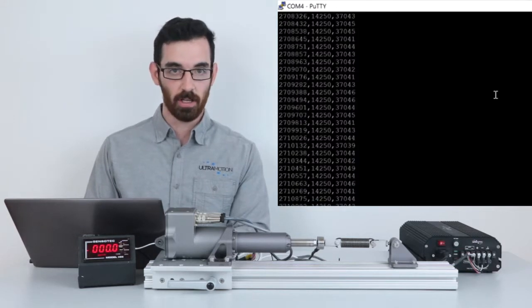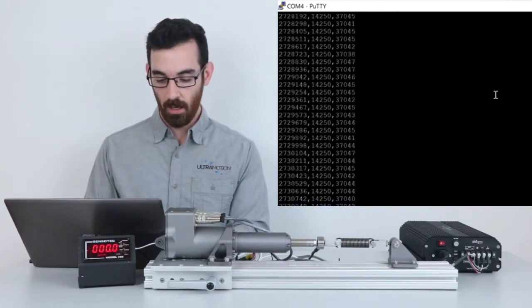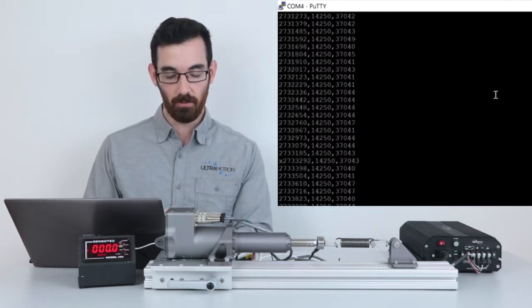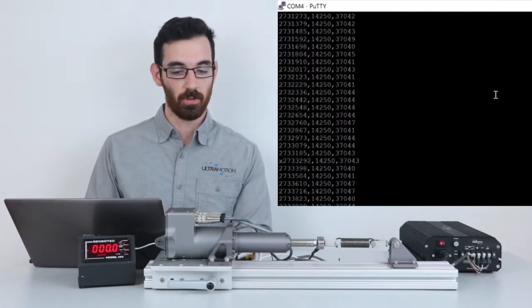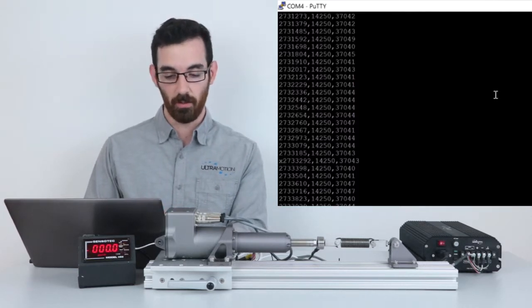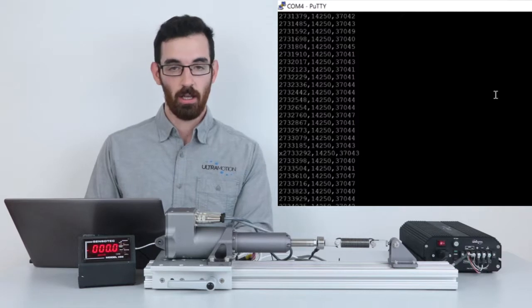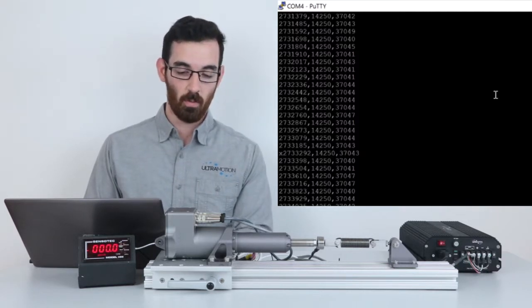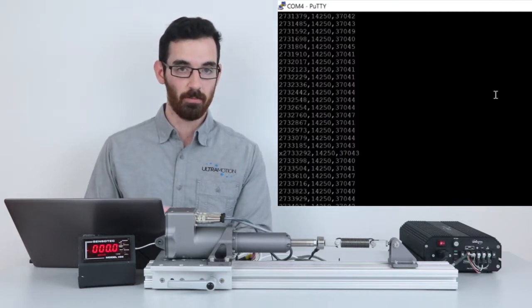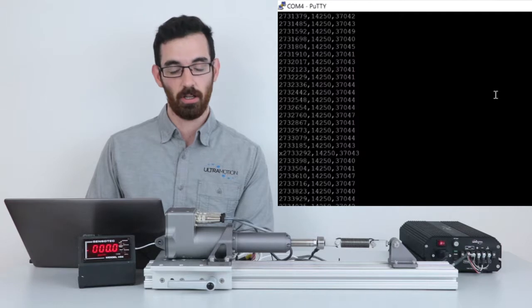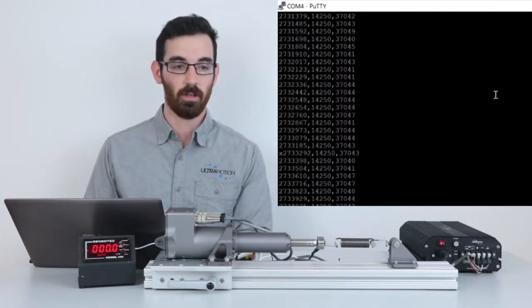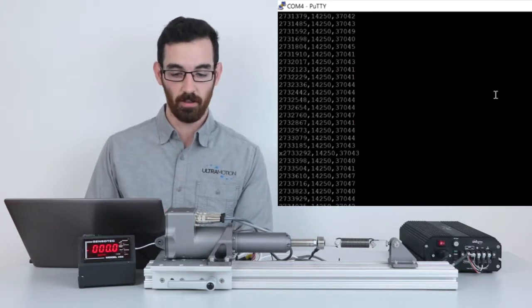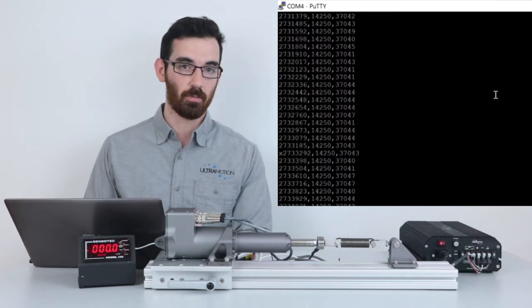If I am not communicating over serial in this manner and I would rather have a PLC or a microcontroller or LabVIEW do it for me, it's typically better to operate in what we call machine mode where it eliminates the detailed messages to the user. It also includes a checksum to ensure your data is good and it includes an acknowledgment or a NACK if the command is bad.